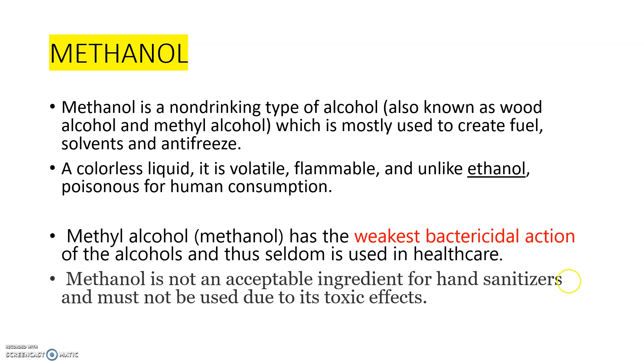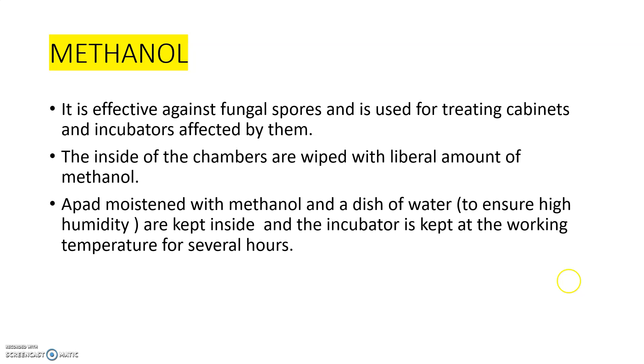But in older times it was used against fungal spores, for treating cabinets and incubators affected by them. This is how it can be used inside the chambers: the cabinets are wiped with a liberal amount of methanol, and a pad moistened with methanol and a dish of water are placed inside. Why do we place this dish of water? To ensure high humidity. Those are placed inside the incubator, and the incubator is kept at working temperature for several hours. Like that, methanol can be used to treat fungal spores.